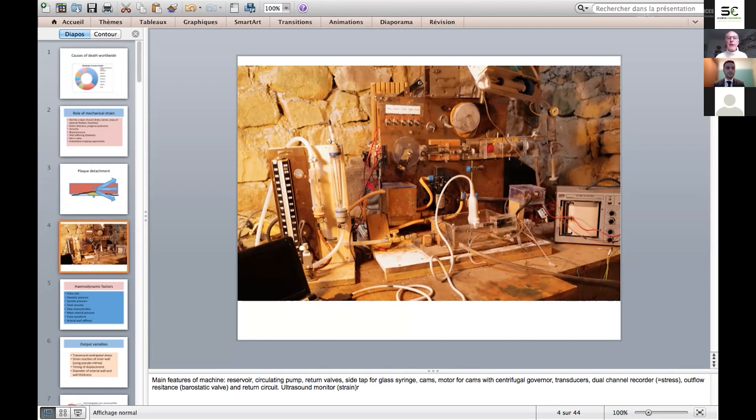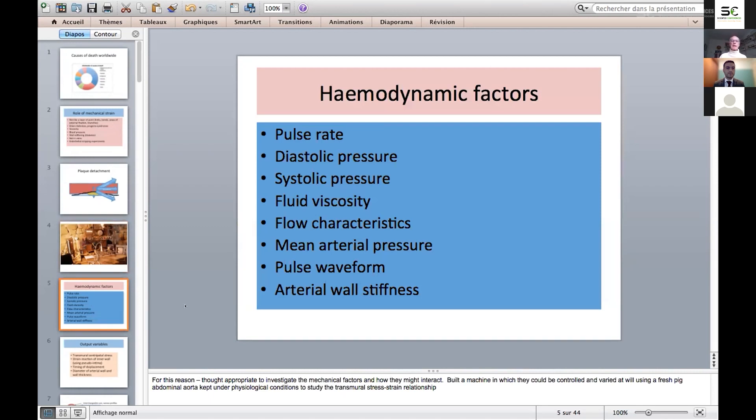The other thing about the machine is that we can change the pulse pressure waveform profile by driving a piston using different cams of different profiles to produce different sets of pulse pressure waves, ones with sharp peaks and ones with blunt peaks. We can vary the rate of pulsation, the diastolic pressure, the systolic pressure, the fluid viscosity, the mean arterial pressure, the pulse waveform, and the stiffness of the arterial wall through various ranges of stiffnesses.